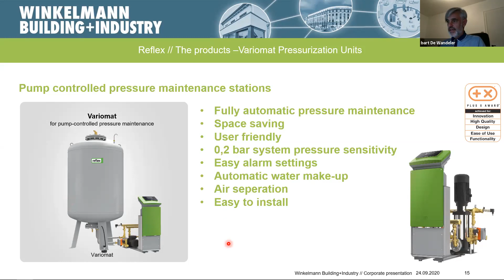The system also stabilizes the pressure within 0.2 bar. The compressor does it within 0.1 bar, but for the pump systems we take a little bit higher range because otherwise the pumps would cycle too much and go on and off. We also have automatic water makeup included, so it will automatically provide the water reserve in the expansion tank. We have a kind of automatic air separation, which I will explain a little bit. And of course, it's also quite easy to install. It's not so difficult.